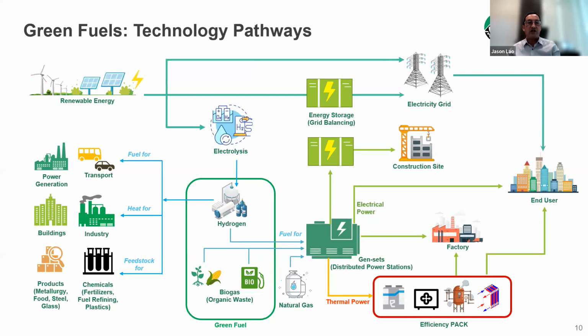For energy usage, one really important part is increasing the efficiency of energy power. For example, for genset applications, we can include an efficiency pack. The efficiency pack can include ORC, which makes use of waste heat to produce power, and CHP, CCHP, which also makes use of thermal power to further produce hot water, steam, or through an absorption chiller to produce air conditioning. So this is another way for us to increase the efficiency of energy power.